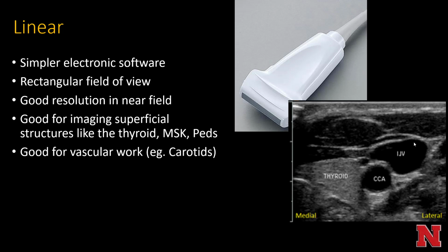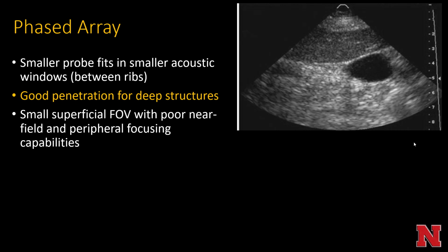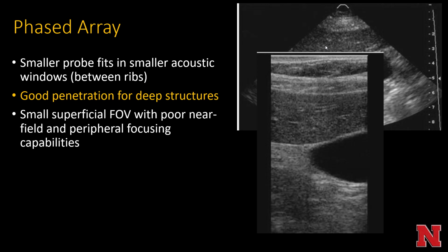Here's a phased array transducer. It's got a smaller probe that will fit in smaller acoustic windows, like between ribs. It has great penetration for things deep in the abdomen or pelvis. This small superficial field of view has very poor imaging in the near field, however, so you wouldn't want to use it for the applications you'd use the high-frequency linear transducer for.